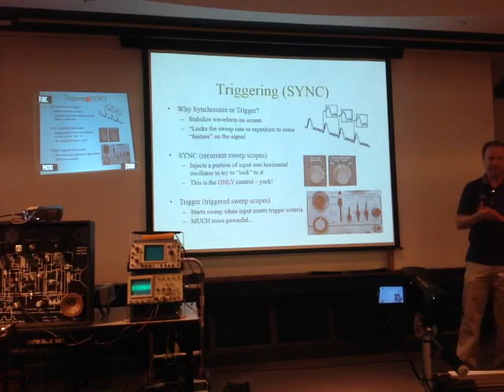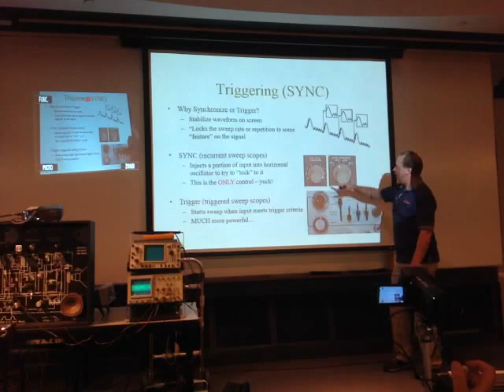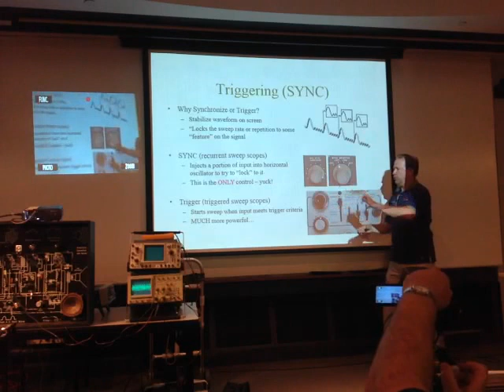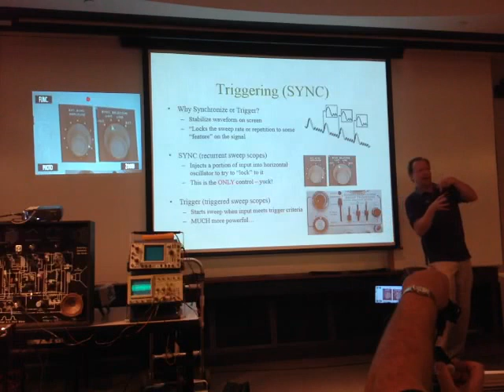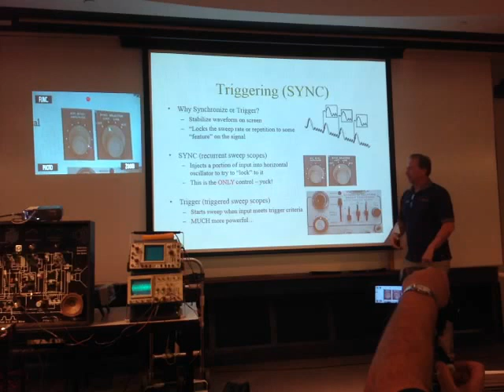Same reason. Okay? Again, these old recurrent sweep scopes will generally have an external sync amplitude, okay, or an internal sync selector, and this amplitude basically takes a piece of that input signal and jams it into the horizontal oscillator to try to make it lock, or pull it and lock it to it. Okay, really ugly, doesn't work very well. Okay, and it's the only control you have. Here's my comment on that.